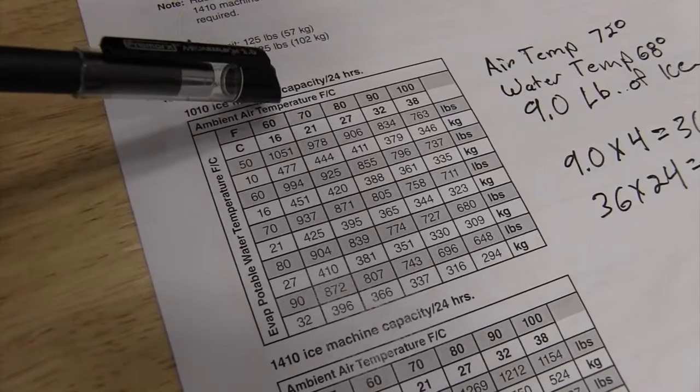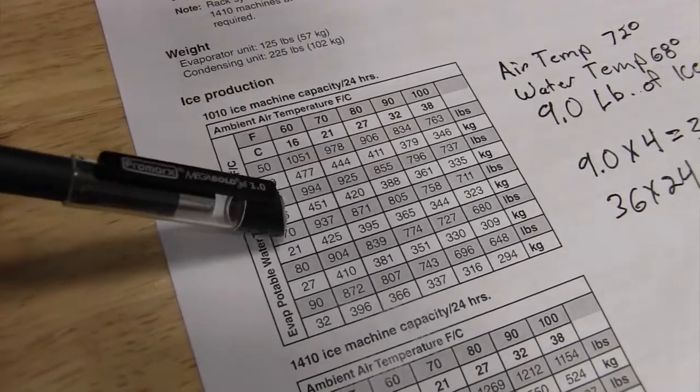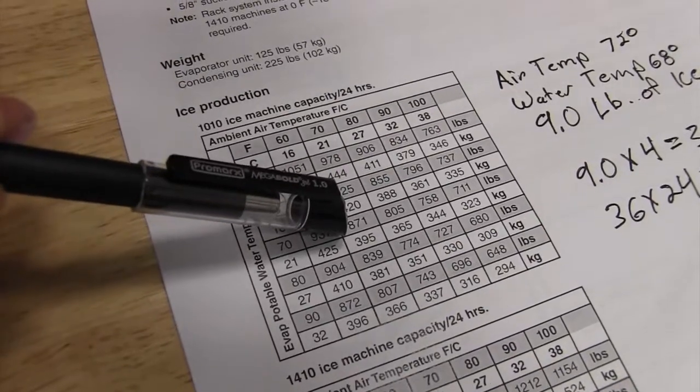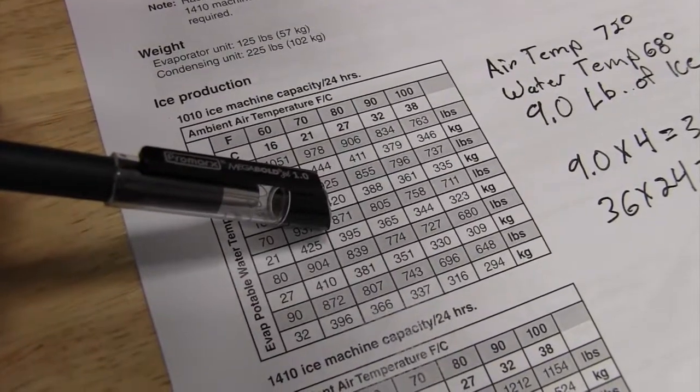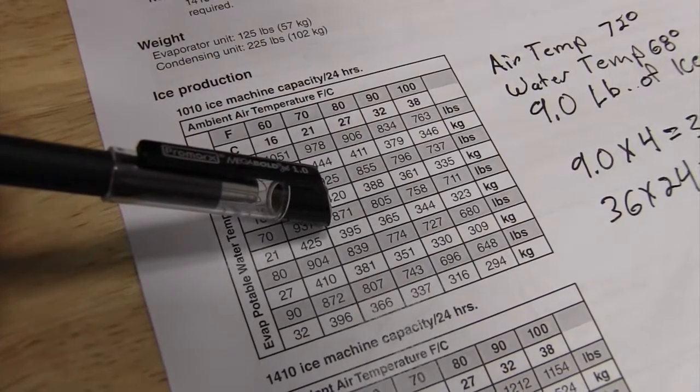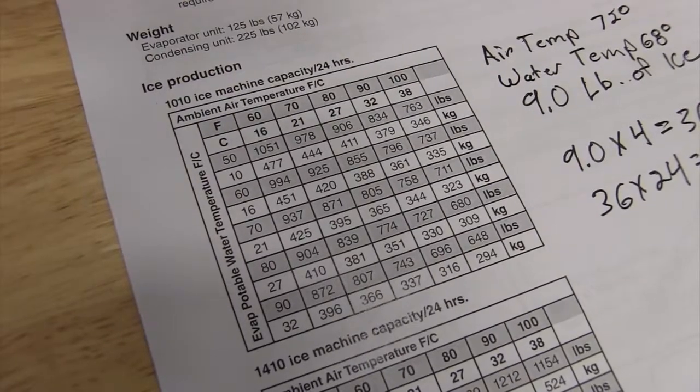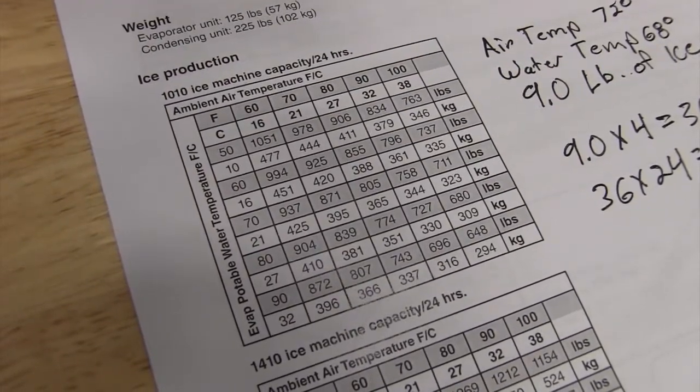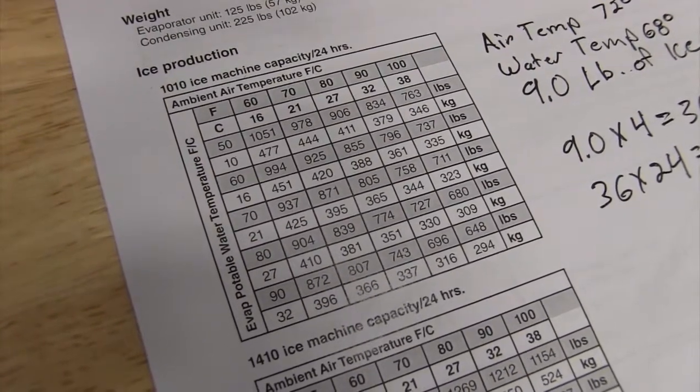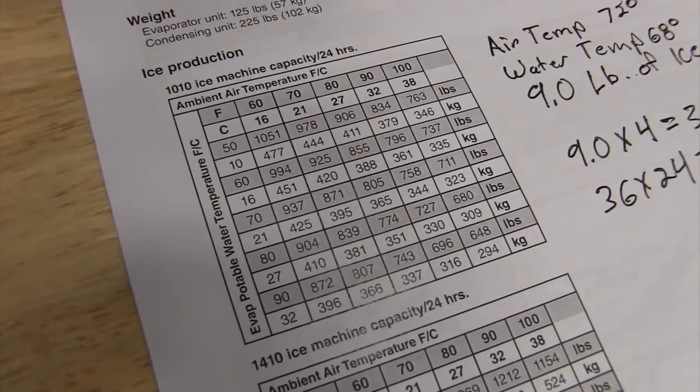On this chart, if we look, we would take our 70 degree ambient air temperature, our 70 degree water temperature, and our expected production rate is 871 pounds. We had 864, we're looking at a plus or minus 10% for our factors. What this is going to do is prove that our ice machine is making good quality ice and it's making the proper production.